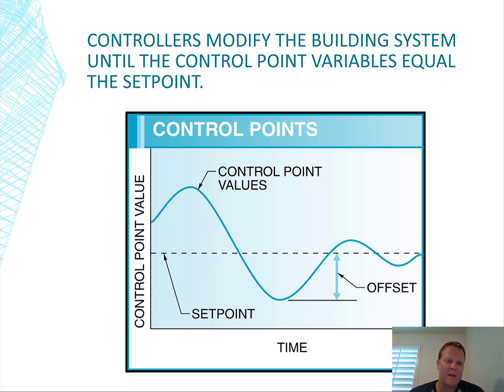And then pretty soon it starts to just crisscross that set point. It usually dials it in, and so with the programming, as soon as something starts up or changes modes, it's usually doing something like this where it's not right on the set point. It's trying to get to the set point, and it might cross the set point multiple times. And I think that's important for people to understand. I liked that comment because it's not wrong to have it do this. This is common.